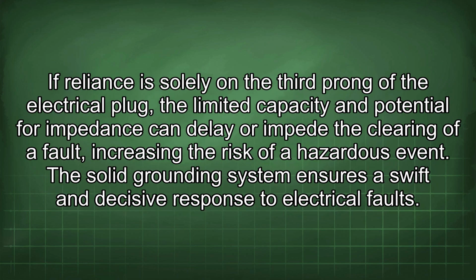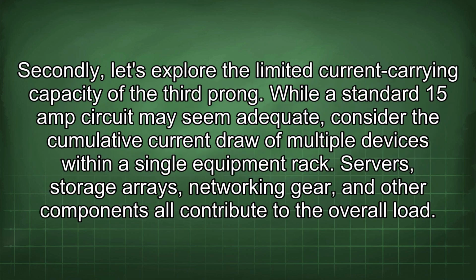If reliance is solely on the third prong of the electrical plug, the limited capacity and potential for impedance can delay or impede the clearing of a fault, increasing the risk of a hazardous event. The solid grounding system ensures a swift and decisive response to electrical faults. Secondly, let's explore the limited current carrying capacity of the third prong.